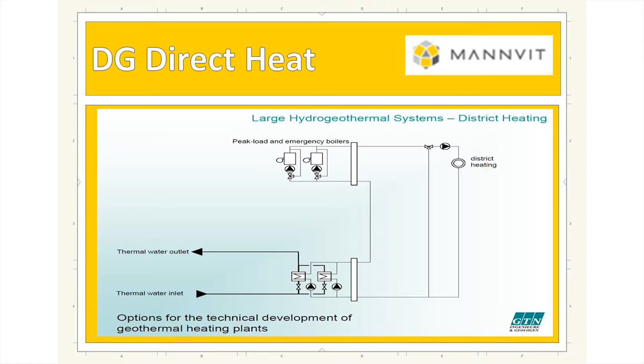What we decided here was the best way to get the maximum out of the wells: we had 55 degrees at depth that we were going to be abstracting, and then using the heat pump, we dropped that temperature down to 15 degrees, so we had a 40-degree delta T, and we ramped it up to a useful temperature.